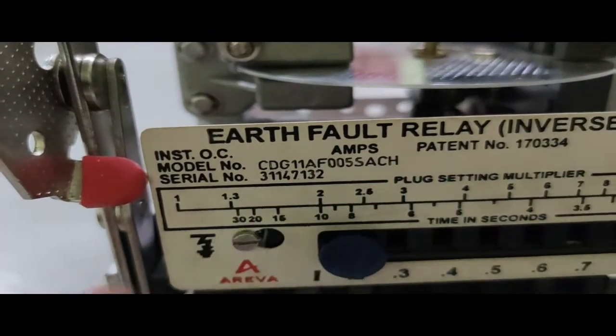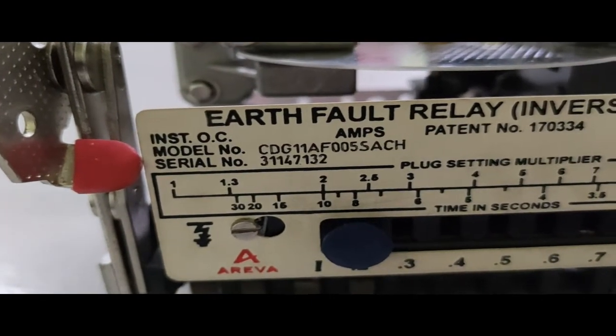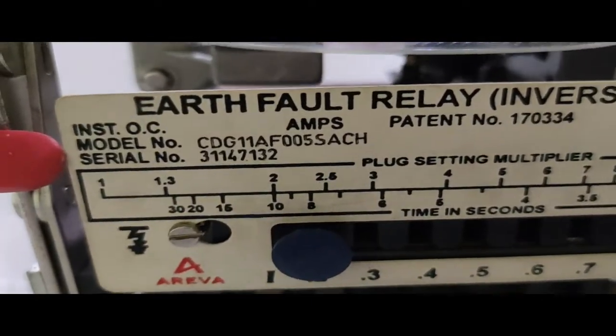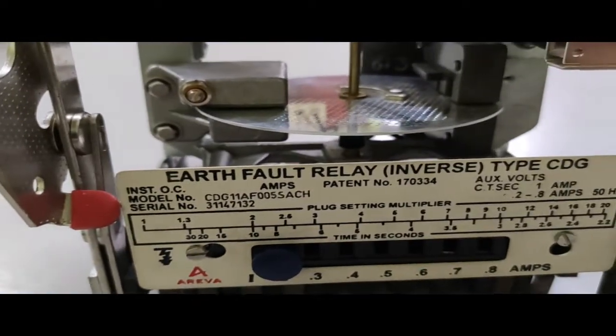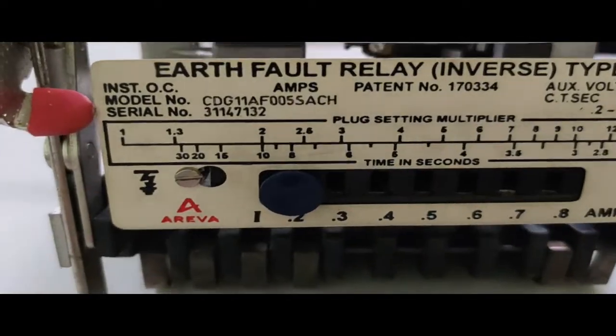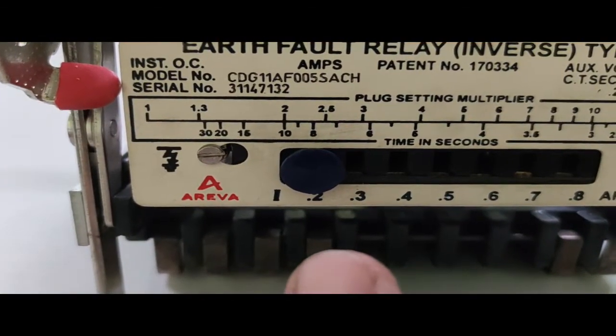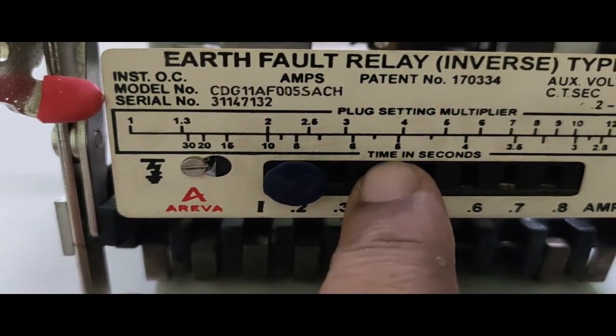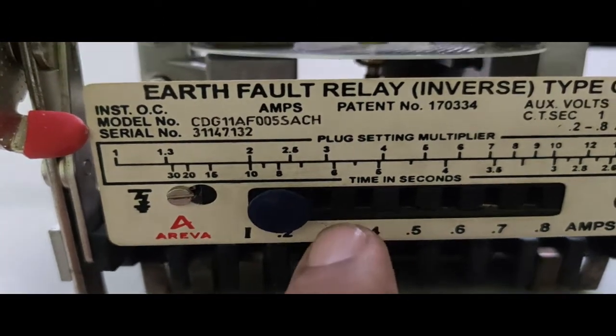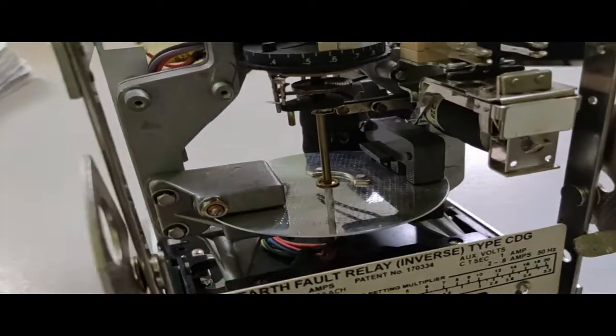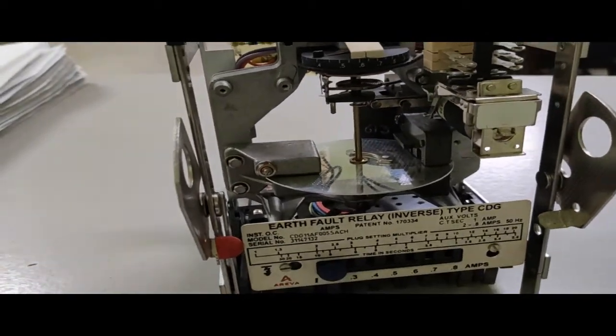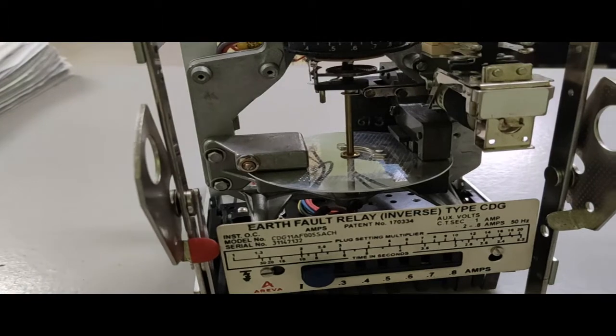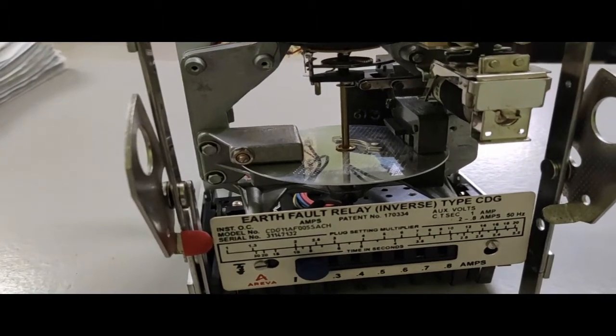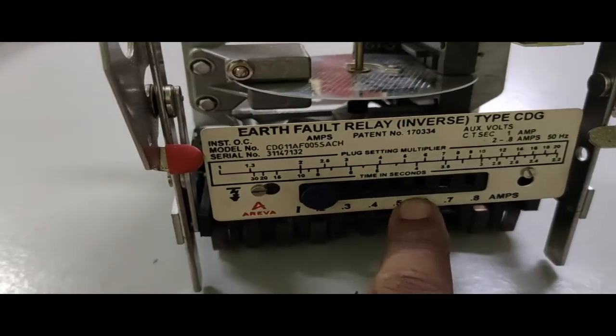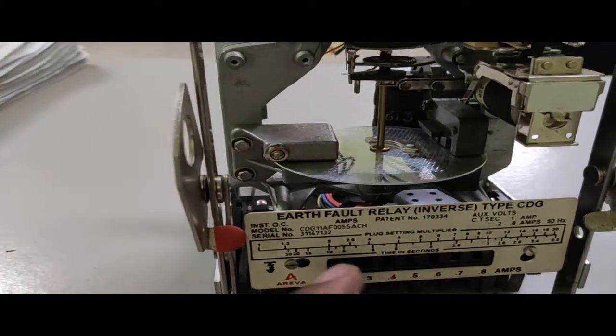Now as this is the earth fault relay, the current rating of the relay should be very small. The relay is connected in series with the path where the earth is connected, and if some leakage current flows to the earth, and if the current is more than 0.2 ampere, then the relay should operate. So this is the plug setting of the relay. Now this is an overcurrent relay. Overcurrent relay means the actuating quantity of the relay is current. If the current is beyond some prescribed limit, then the relay should operate.